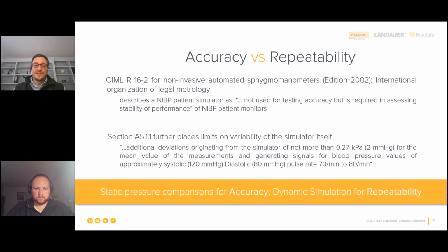We have a number of webinars on NIBP where you can learn more about measuring repeatability and how you can use the envelope shifts to do so. I won't get into that today, but the main takeaway is: static pressure is used for accuracy, and you use the dynamic simulation for repeatability. It comes up time and again from tech services, but there really is no way to measure dynamic simulation accuracy. So, a lot there. It's meaty, there's a lot behind it, but that's what I want you to take away.